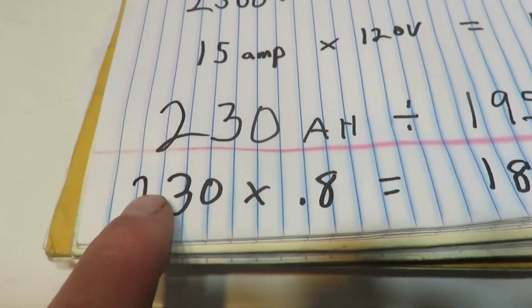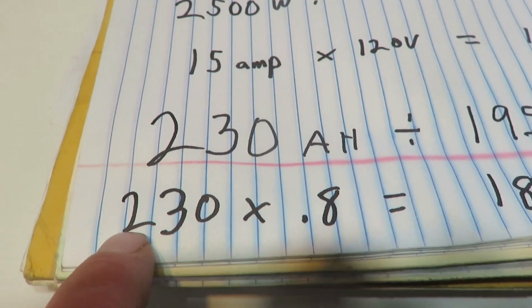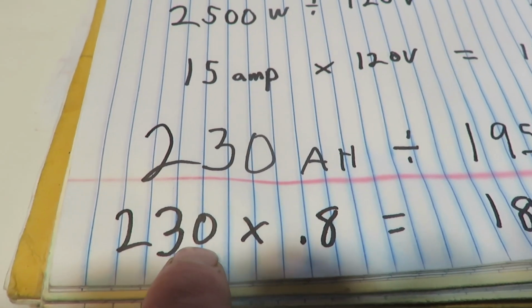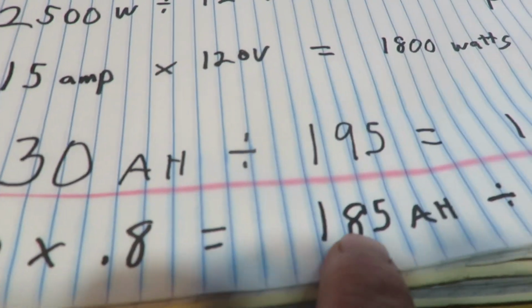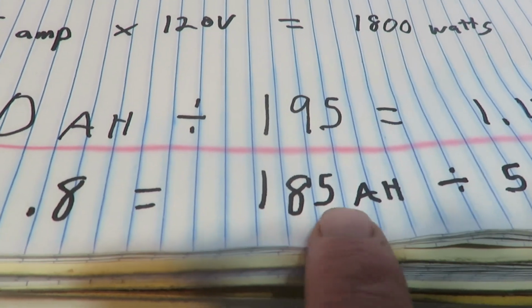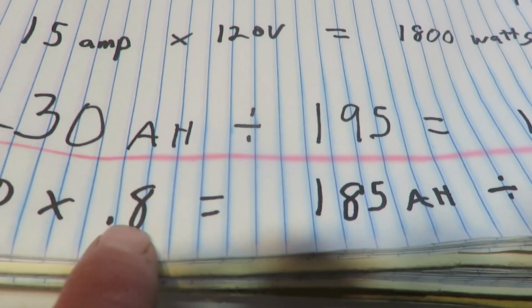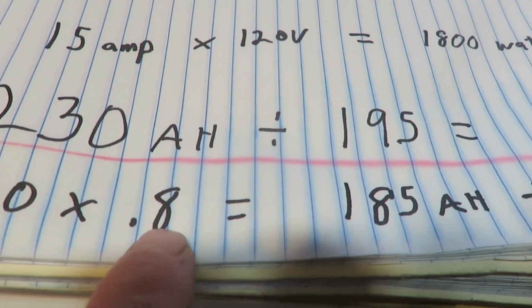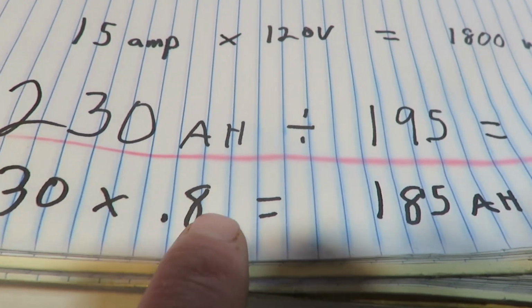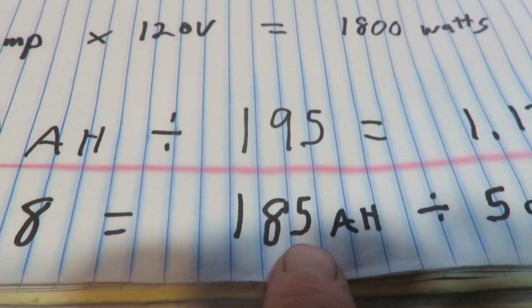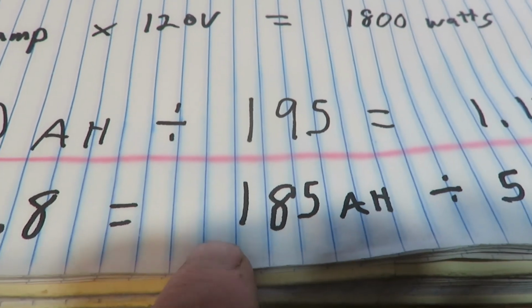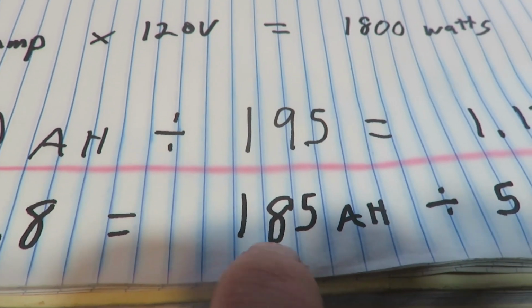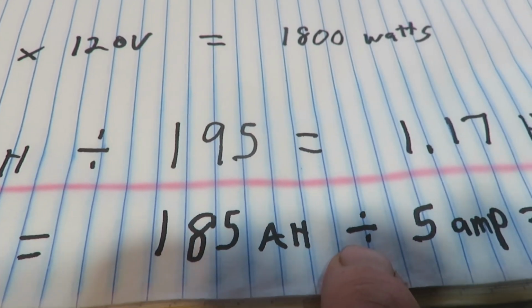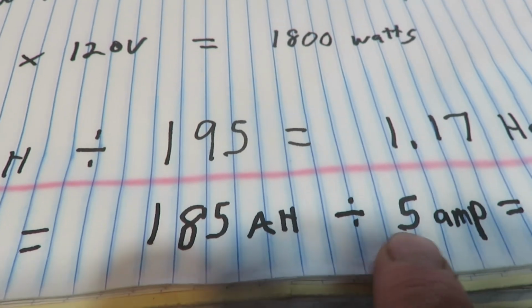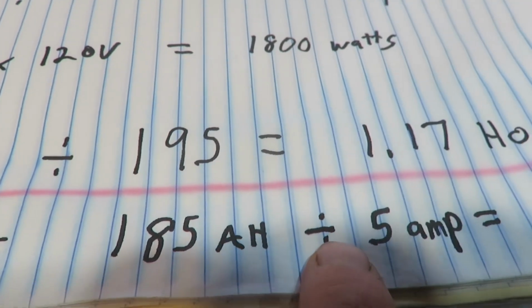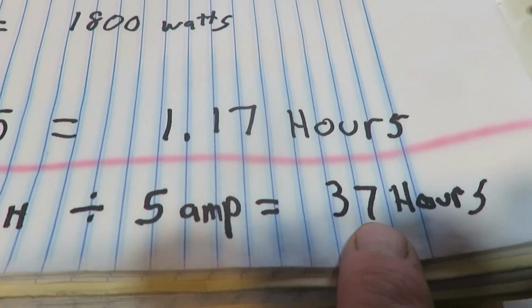Okay, I just did the numbers for more realistic. 230 amp hour battery times 0.8, that would be 185 amp hours, because you're not going to go below the 20%. You'll take 80% out of it. So realistically you are looking at something more like 185 amp hours. And if you were running a 5 amp load, divide that by 5 amps, you'd have 37 hours.